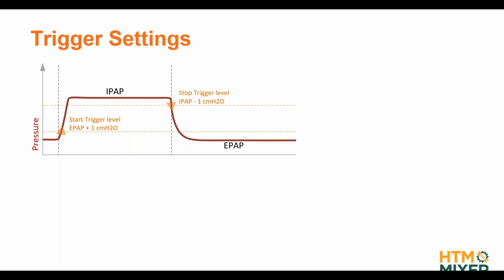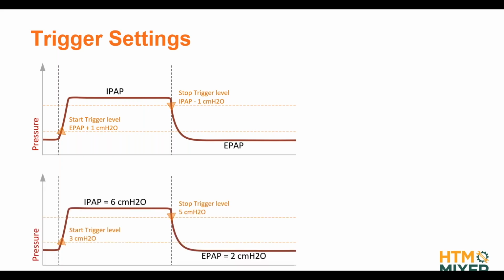The problem here is that your trigger settings are no longer independent of the settings of your analyzer. Because let's consider the first setting that we need to test in our service procedure is IPAP of 6 and EPAP of 2. So our levels would be at 3 and 5 to trigger. And let's assume the next setting we need to test is IPAP of 8 and EPAP of 4.